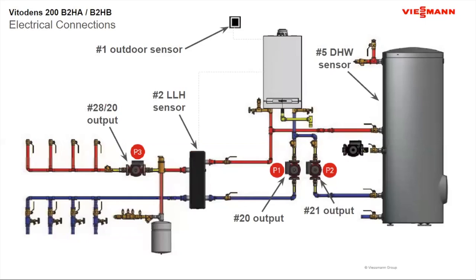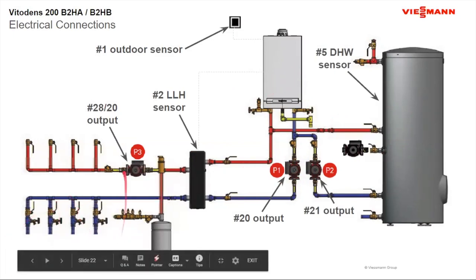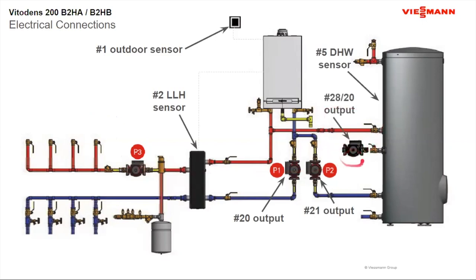Looking at pump placements on the piping diagram: the number 20 pump output is our boiler pump, which activates the flow switch or flow sensor inside the boiler. The 2820 pump output can be either a system pump or a recirculation pump. When programming, there are time programs for DHW recirculation — meaning a loop constantly circulating hot water around the house so you have hot water immediately when you open a faucet. You can program the times you want it to run and shut off.